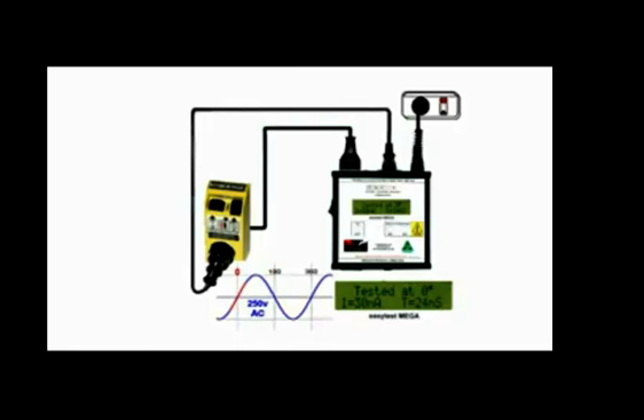Since the RCD is an electromagnetic device, it's industry best practice to reverse the phase angle and check the switch times when the current's flowing in the opposite direction. So the Mega automatically changes phase by 180 degrees every time you press the button. So reset the RCD and perform the test again. Record the results at 0 degrees and 180 degrees and you'll keep the auditors happy. In the event that in either case the trip time exceeds 300 milliseconds, it'll simply show as a fail.